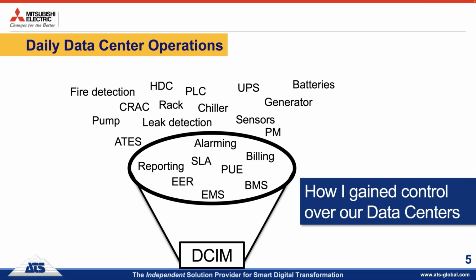For instance, if there was a CRAC unit in alarm, I could immediately see the surrounding crack units, the room temperature, the pressure in the room, but also the pumps in the chilled water system, the CRAC units, hybrid dry coolers, or everything feeding into those cold water systems. I could even see the power monitoring on those parts, and that gave me immediately a lot of information needed to assess what was going on and determine the first actions to resolve the issue quickly. This resulted in less downtime and less risk of potential loss of services to customers. So it gave me a true real-time overview of every part of the data center.